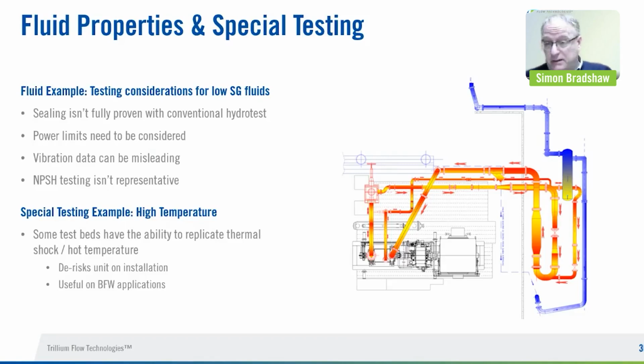Power limits need to be considered. As I mentioned, vibration can be misleading because now you're putting much more power into the pump than you would be at site. So that again needs to be a discussion between the purchaser and the OEM about how vibration is going to be measured and how it's going to be recognized whether something is acceptable or not. This is particularly the case because sometimes you have to run it at a different speed, and then it gets quite interesting. And NPSH testing isn't necessarily representative.